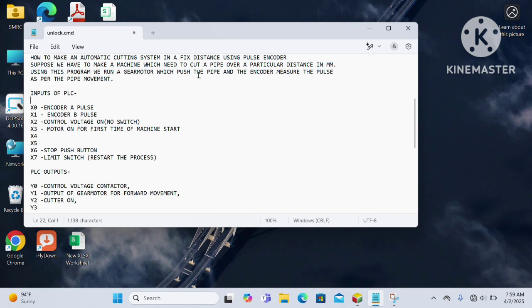X0 is used for pulse A of the encoder, X1 for pulse B of the same encoder. X2 is for the control voltage push button which enables power on the circuit. X3 is to enable the gear motor. X6 is the stop push button which stops the whole circuit, and X7 is the limit switch for the cutting point. You can see the outputs of the PLC similarly.